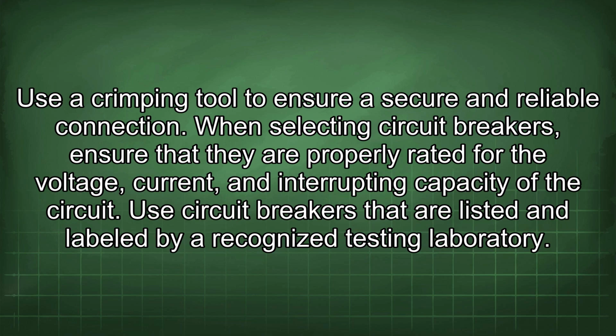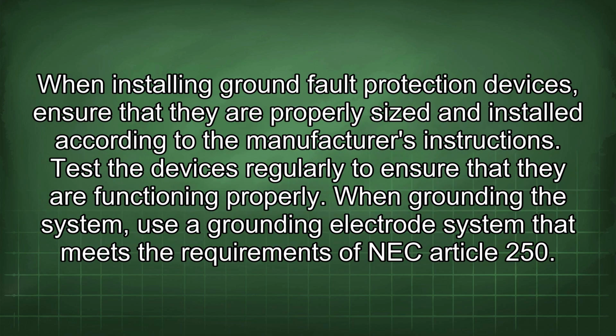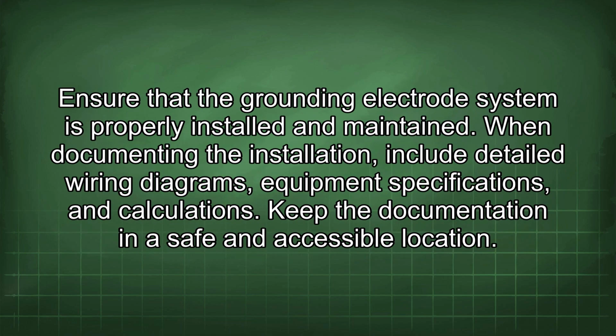When selecting circuit breakers, ensure that they are properly rated for the voltage, current, and interrupting capacity of the circuit. Use circuit breakers that are listed and labeled by a recognized testing laboratory. When installing ground fault protection devices, ensure that they are properly sized and installed according to the manufacturer's instructions. Test the devices regularly to ensure that they are functioning properly. When grounding the system, use a grounding electrode system that meets the requirements of NEC Article 250. Ensure that the grounding electrode system is properly installed and maintained.